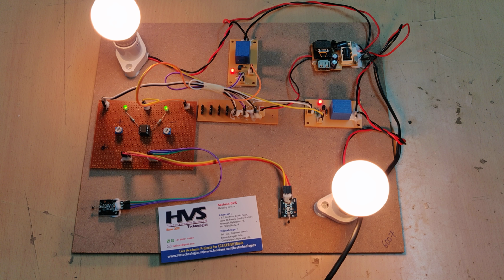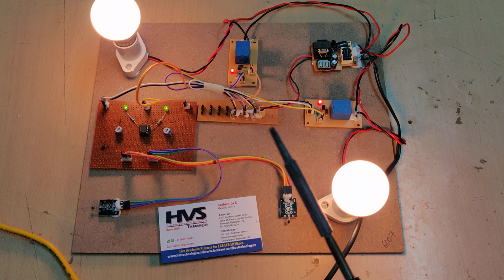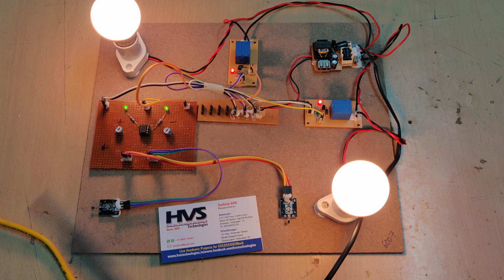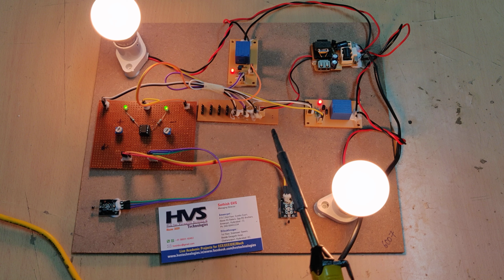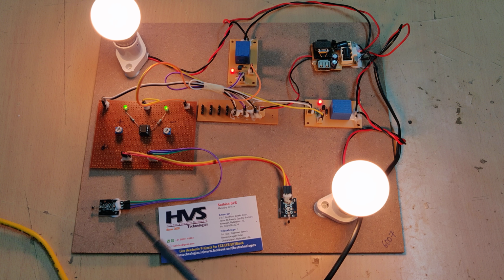Whenever a heavy load occurs on the transformer, the coil's temperature will increase due to that heavy load, and that temperature is cooled down by the transformer oil. If the load keeps increasing continuously, it may lead to transformer damage. We need to detect these temperature threshold values, and in order to protect the transformer from overload, we need to cut off the load to the transformer.